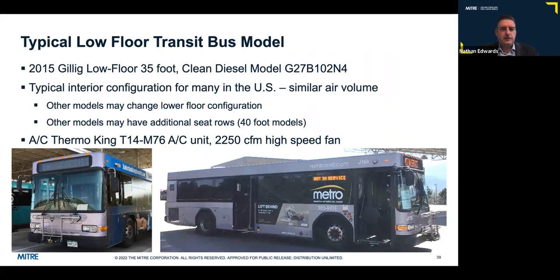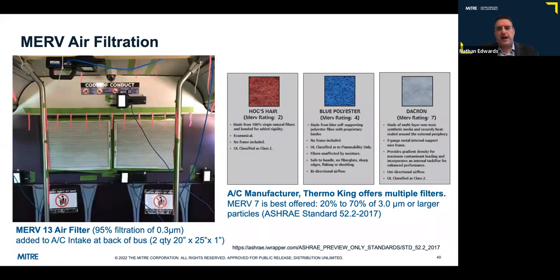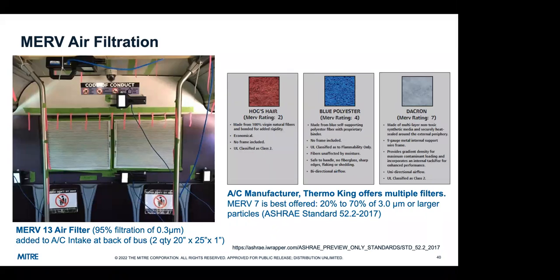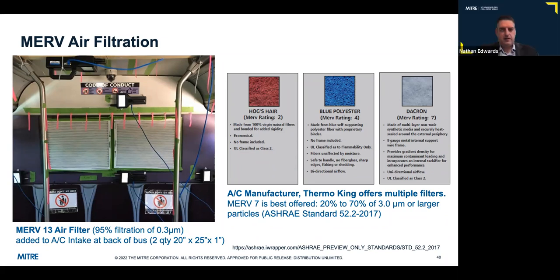The HVAC system had a 2200 cubic feet a minute fan, and the filters in the back, really the manufacturer specified only these, I think MERV 7 at best. And many of you know MERV 7 doesn't really filter much other than a large accumulation of dust, and not really that very well. So we wanted to understand the effect of applying a MERV 13 air filter as part of our experiments. The one challenge, of course, we knew the manufacturers is you have a pressure drop across those filters. Is it enough pressure drop that it's going to cause a motor problem on those blowers? So we want to measure that as well.